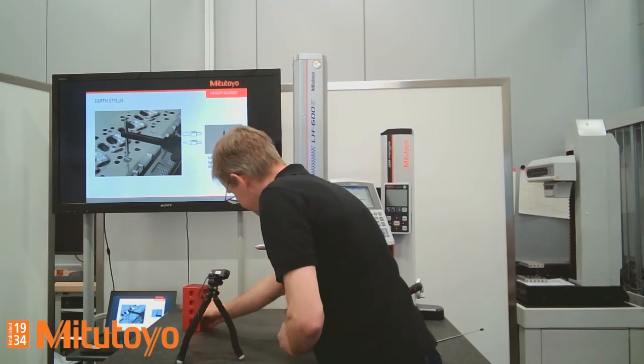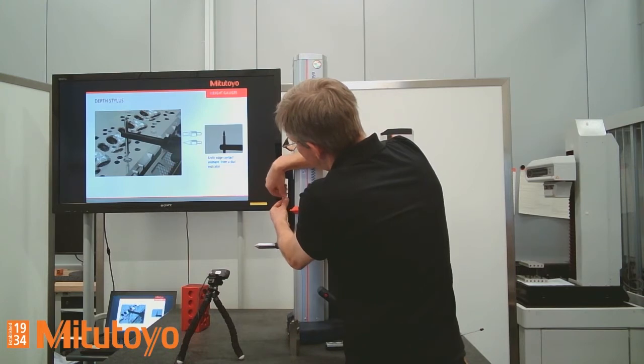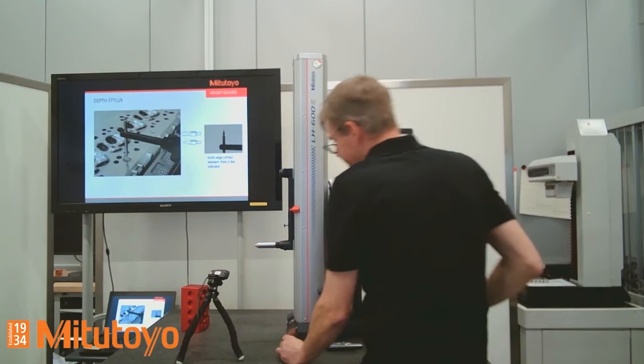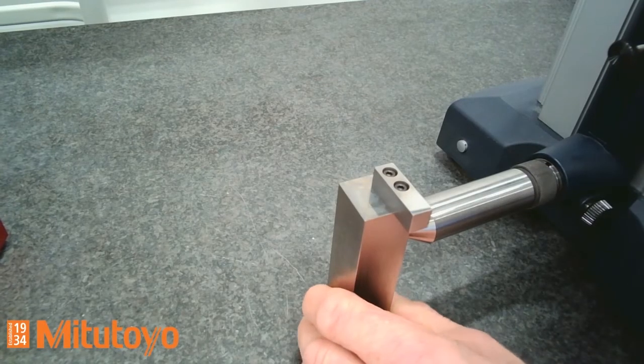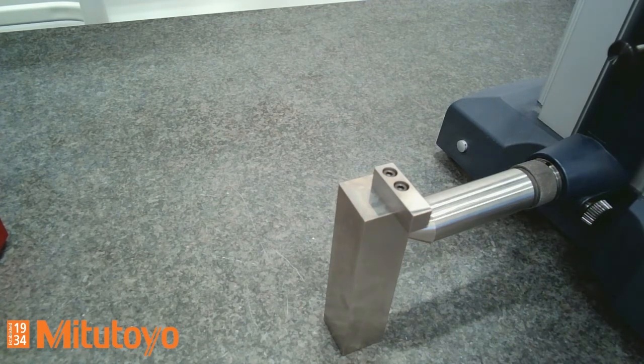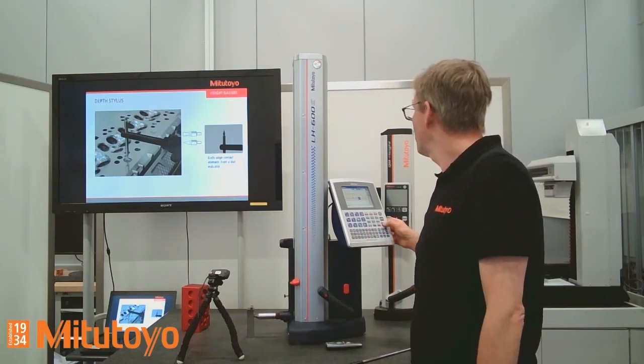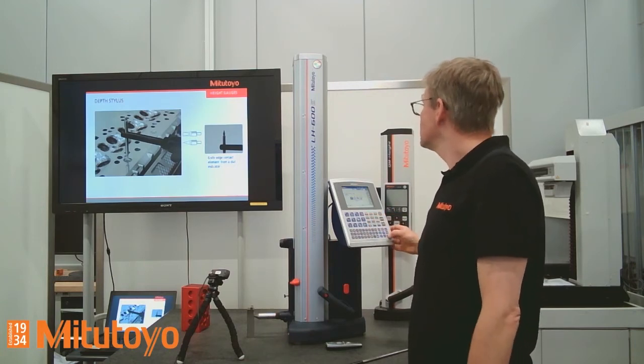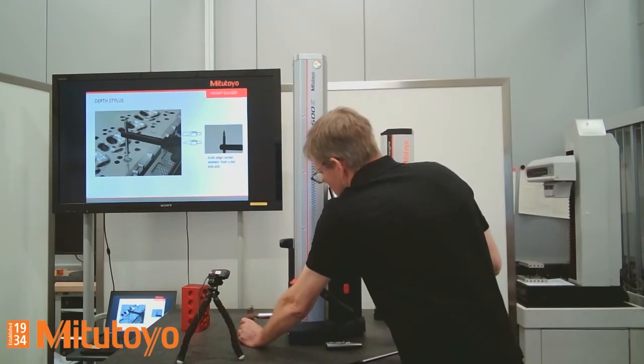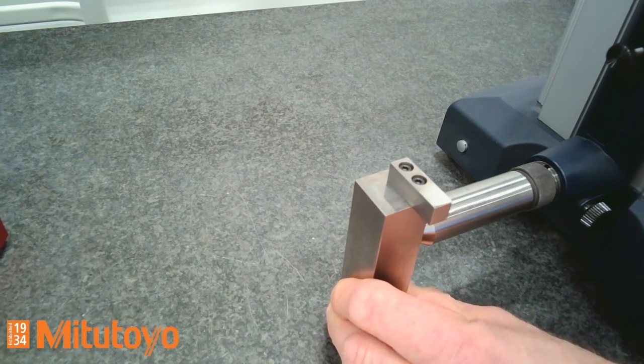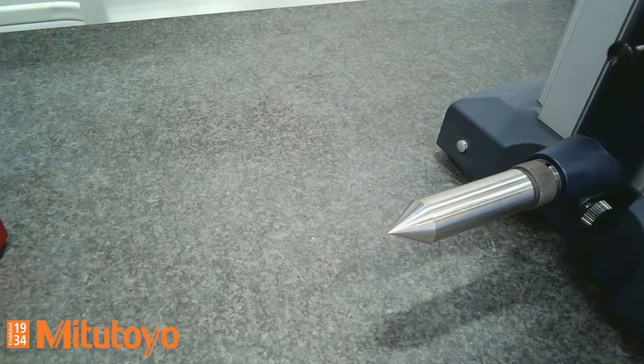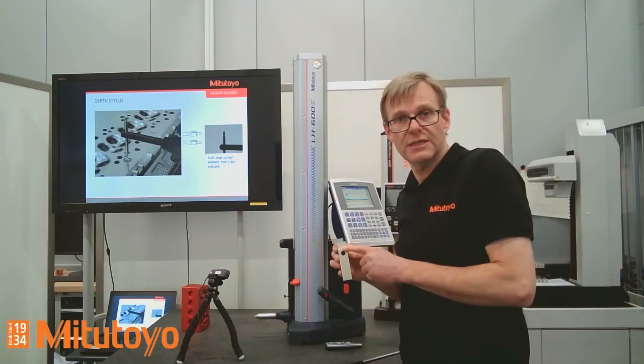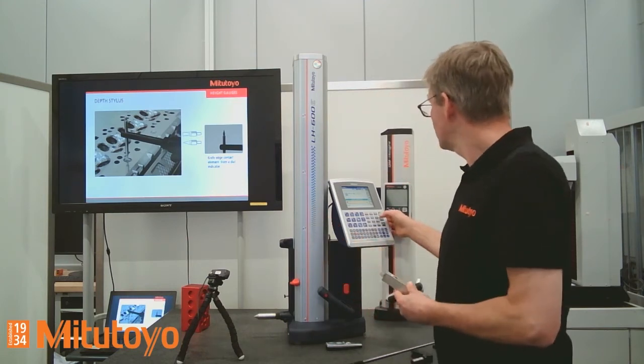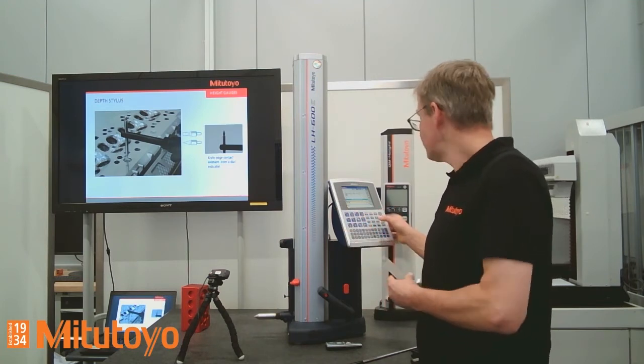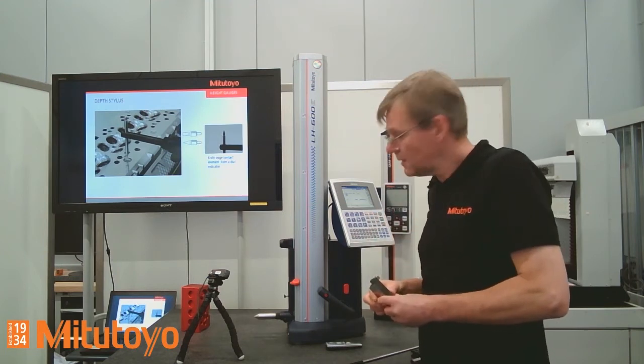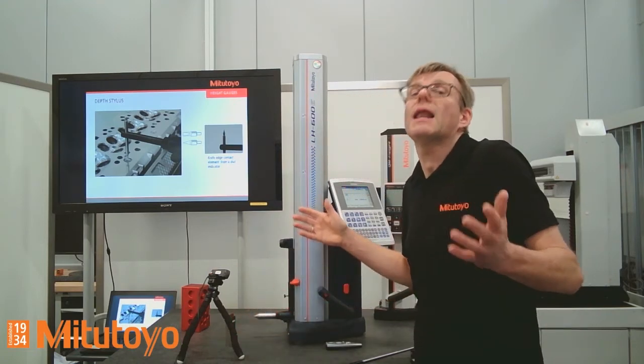Put this one here a little bit beside. Take one of this out. And change again the probe. So I select the taper probe. So, okay, next one. Put this one here in front of the tapered probe. So, and the controller box is asking for the offset value, which is written on this height setting gauge. So here we have 69.785. So that's it. That means this one is now, let's say, calibrated.